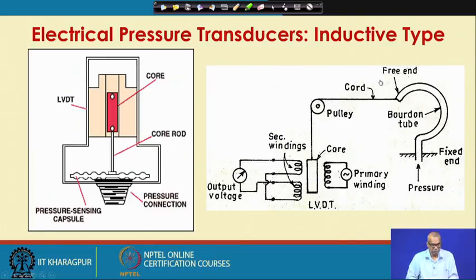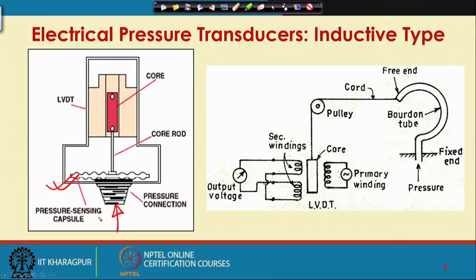This is a better picture of diaphragm based electrical pressure transducers and Bourdon tube based electrical pressure transducers. So, here you have this diaphragm or those capsules. So, you have formed a pressure sensing capsule using diaphragms. You take two diaphragms and join them at the periphery. So, you form a capsule. Now, this is the connection for the pressure.